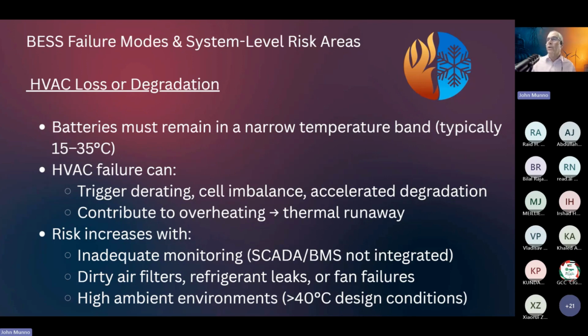I've seen it where the conditions on site are so dusty that the filters need to be replaced more often than what the manufacturer recommends as an average. You have to remember that your site-specific conditions are going to dictate your risk, and all the manufacturers can do is give you a general idea of what they see across their entire fleet. So you have to take your own experience into account when you're dealing with HVAC systems, and if you start to see fan failures, start changing your air filters more often.